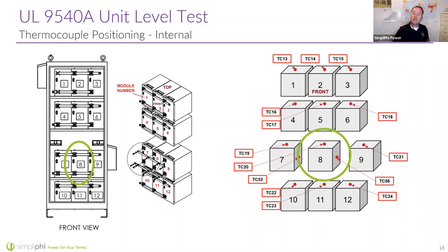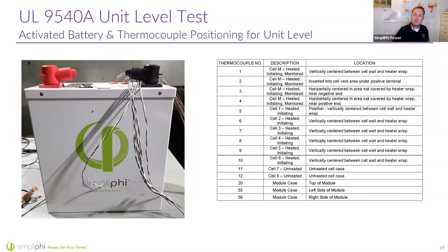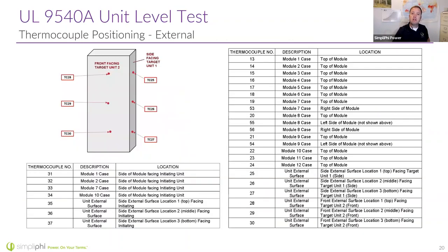So you're going to see thermocouple number 56 show us the highest heat gain of all these thermocouples. And it's actually not that remarkable how hot it gets. Showing the picture again, of all those different thermocouples we're measuring, we also put thermocouples on the exterior of the battery cabinet.